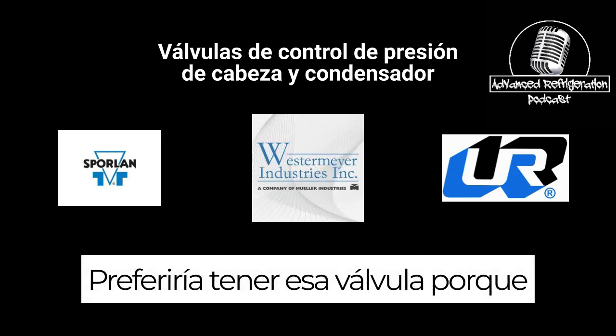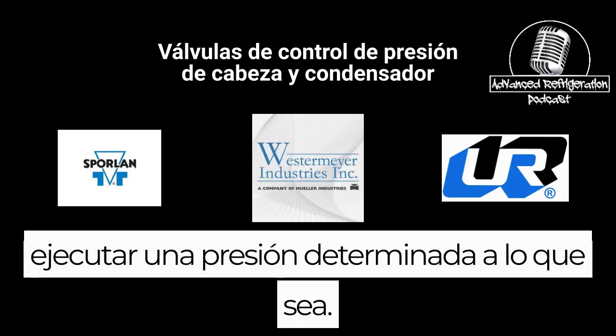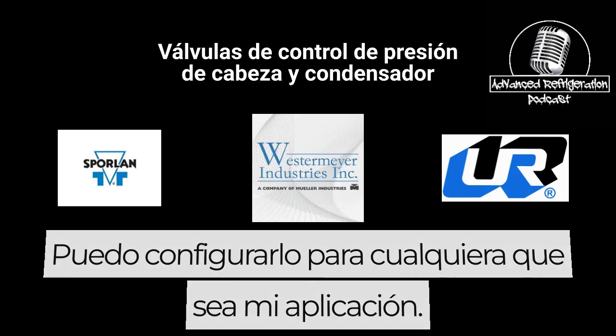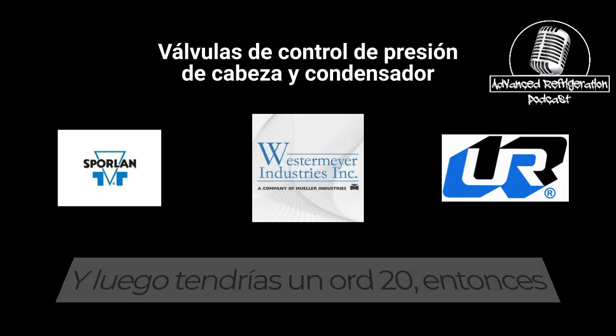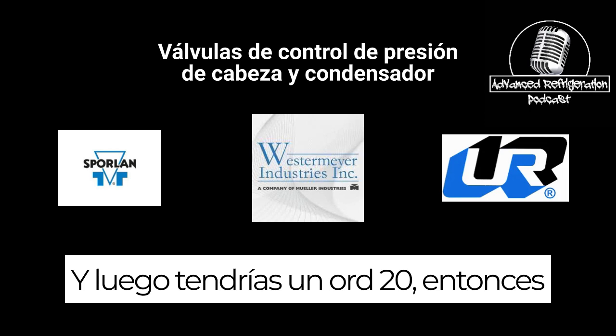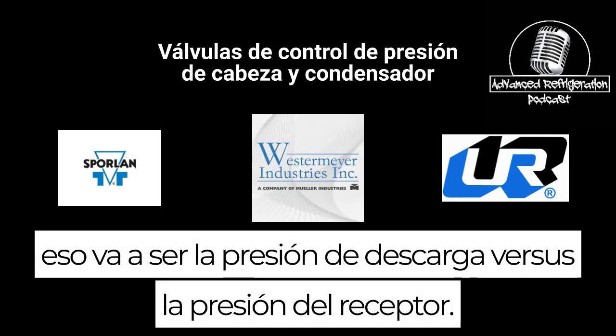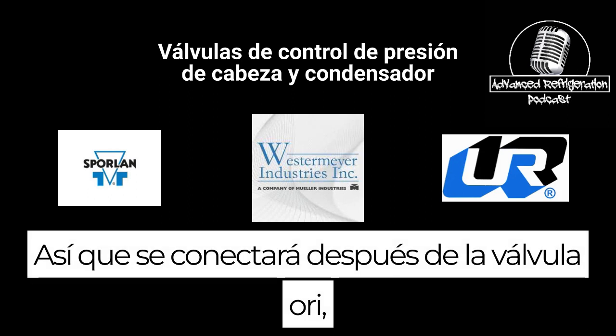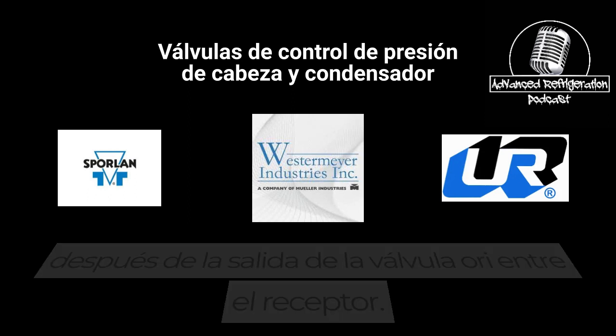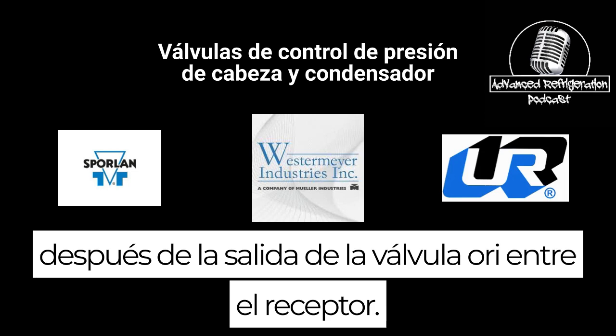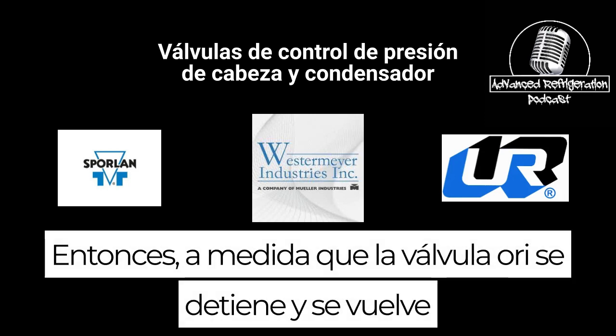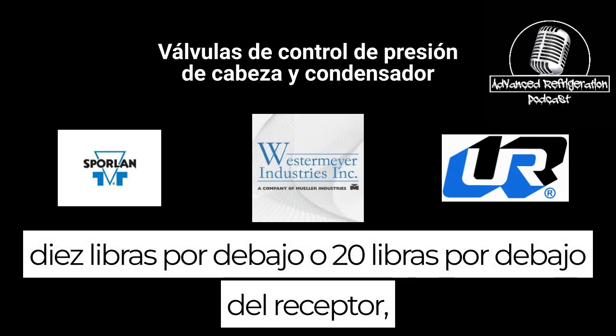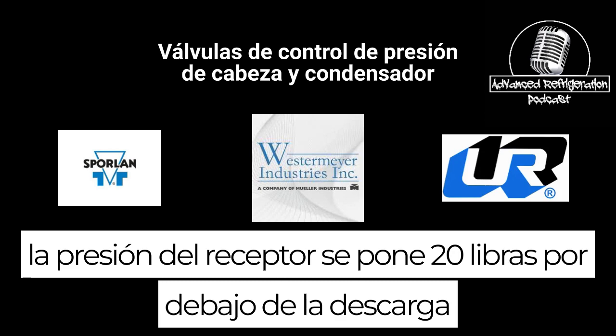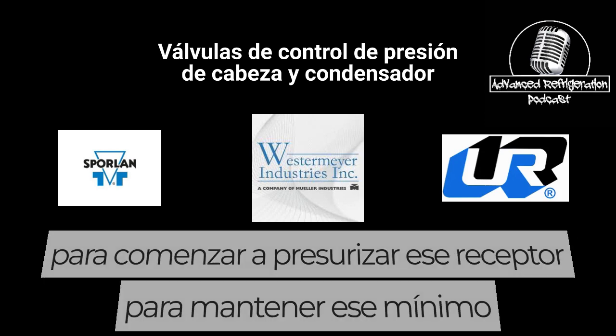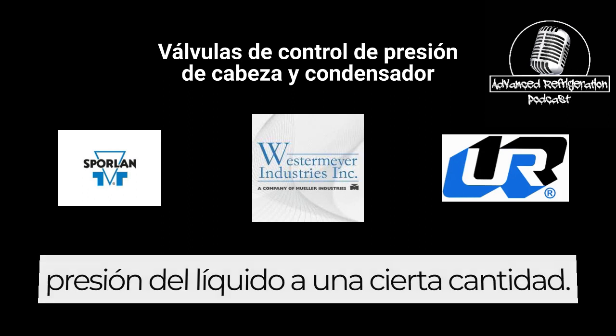I would rather have that valve because I can adjust it, and I don't have to run a set pressure. I can set it for whatever my application is. And then you would have an ORD 20. That's going to be discharge pressure versus receiver pressure. It's teed in after the outlet of the ORI valve, in between the receiver. As the ORI valve holds back and the receiver pressure gets 20 pounds below the discharge pressure, it's going to open up and start pressurizing that receiver to keep that minimum liquid pressure at a certain amount.